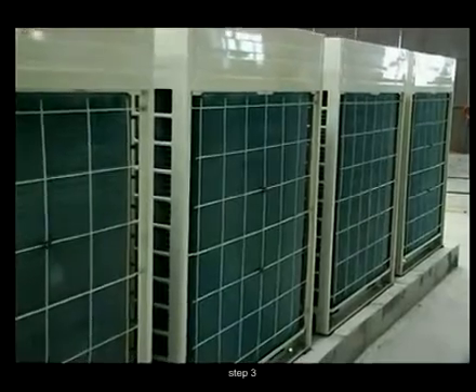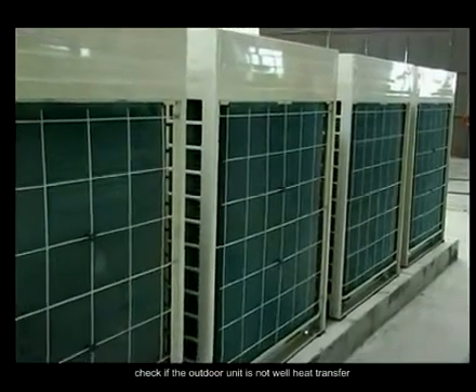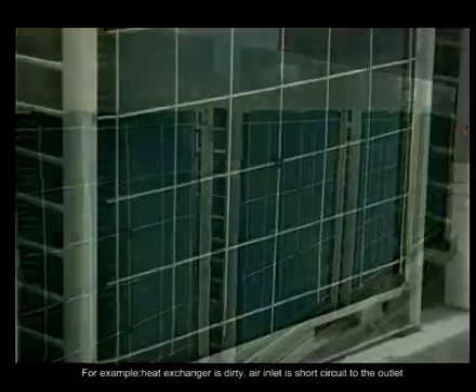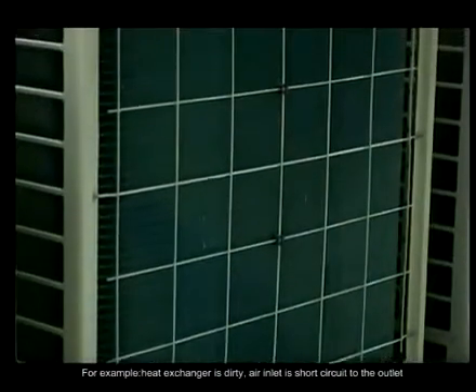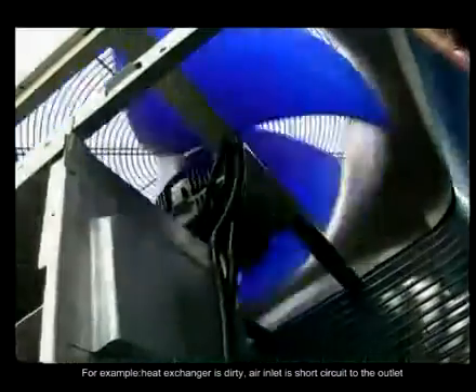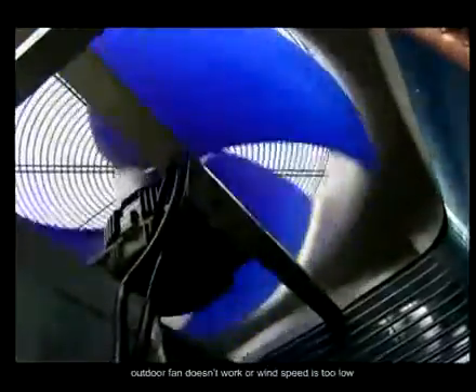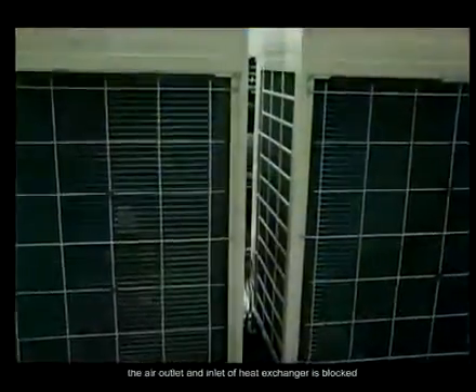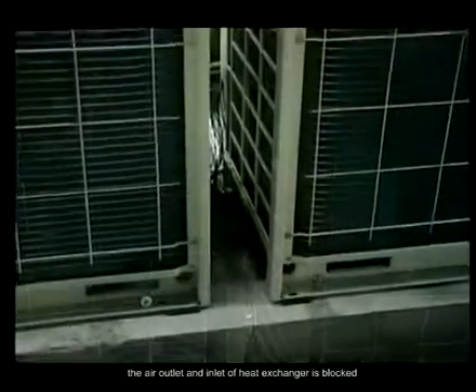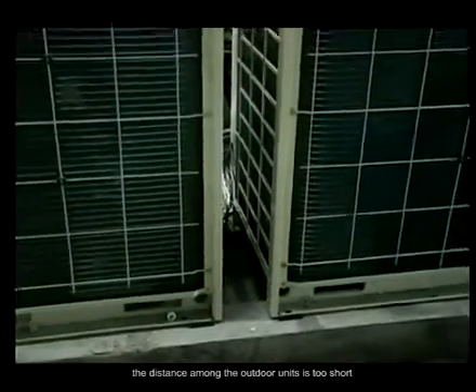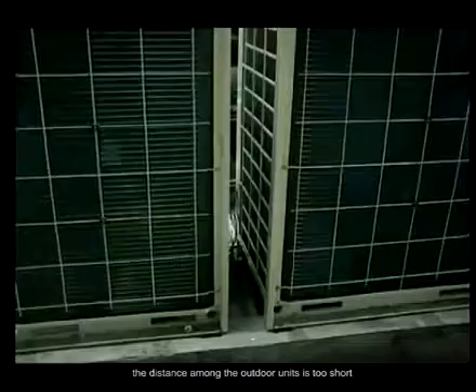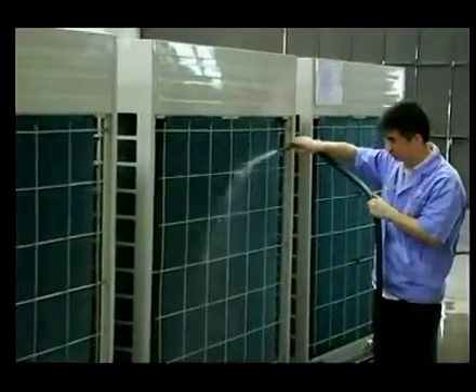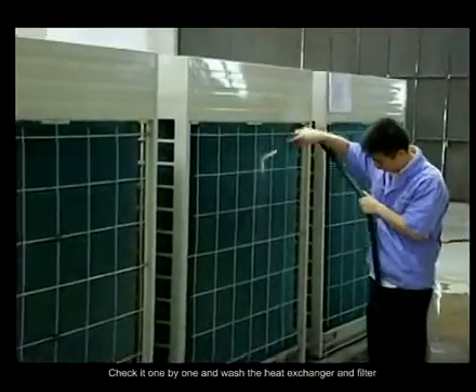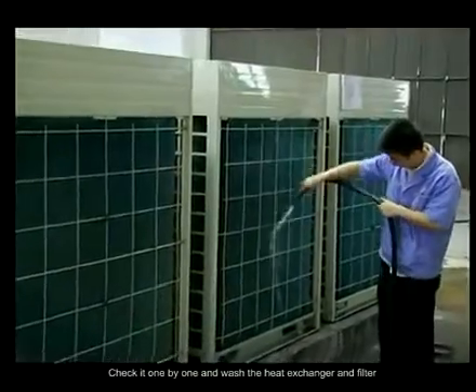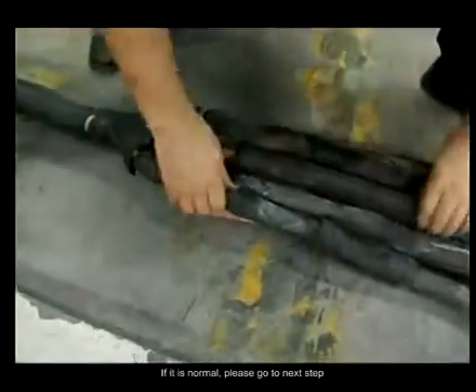Step 3. Check if the outdoor unit has poor heat transfer. For example, the heat exchanger is dirty, the air inlet is short circuited to the outlet, the outdoor fan doesn't work, or wind speed is too low, the air outlet and inlet of the heat exchanger are blocked, or the distance among the outdoor units is too short. Check it one by one and wash the heat exchanger and filter. If it is normal, please go to the next step.